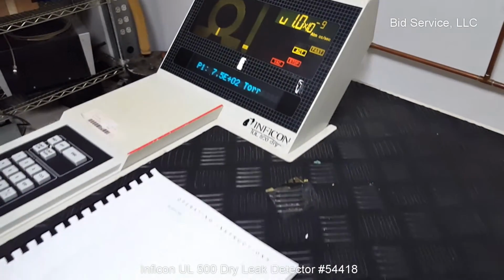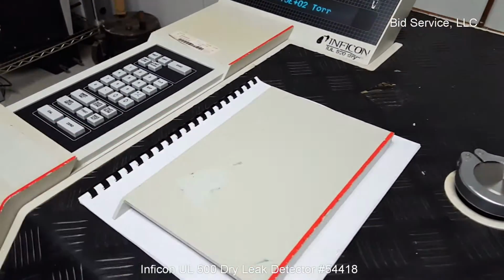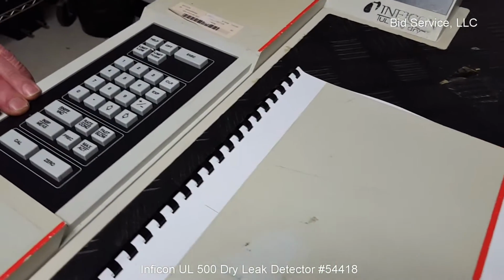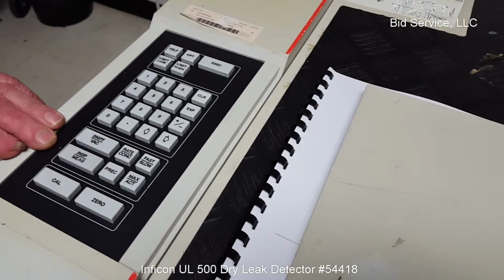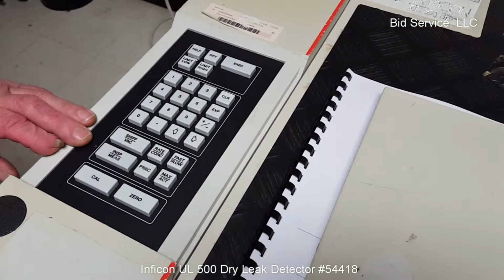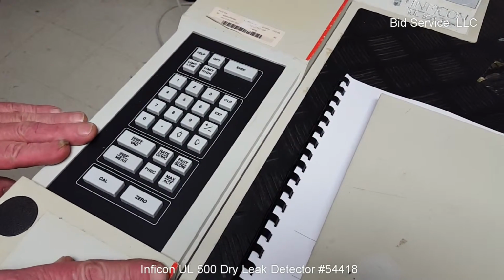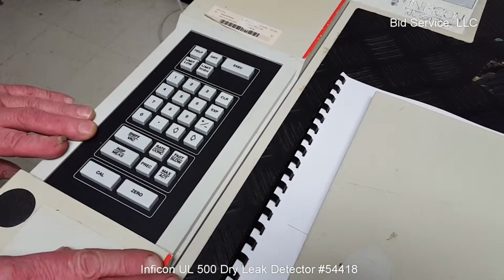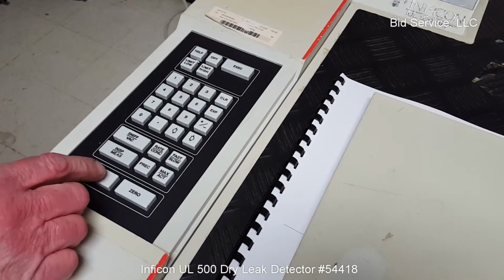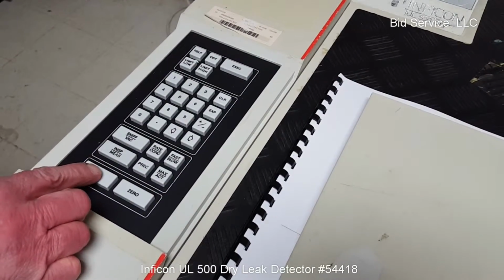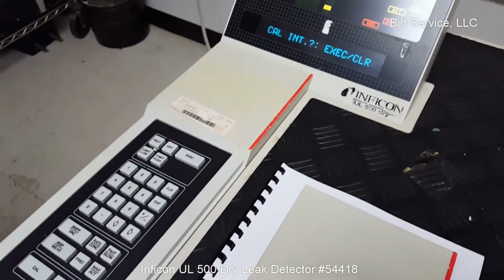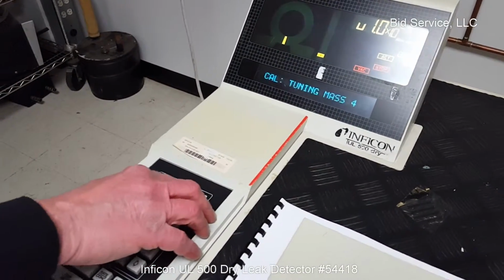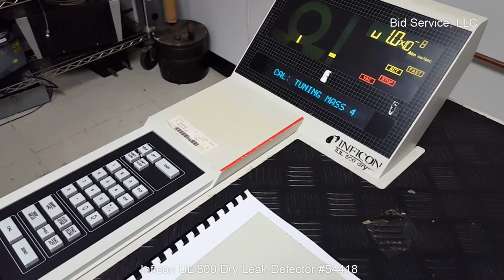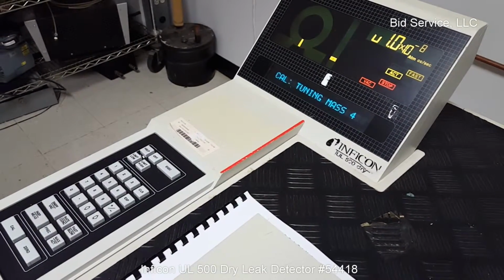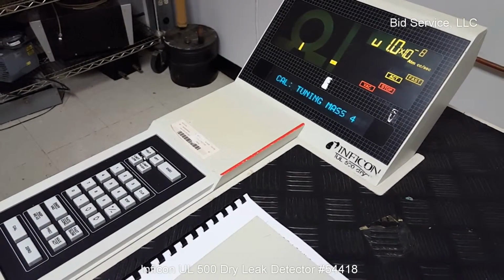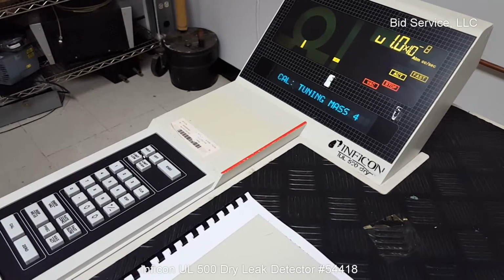Underneath this cover is a control panel that allows you to set different options and configurations for the system. It also allows us to do an internal calibration. It's simply done by pushing the calibration button and then executing. This takes approximately 2 to 3 minutes, and it will calibrate the mass spectrometer to the internal calibrated leak source.